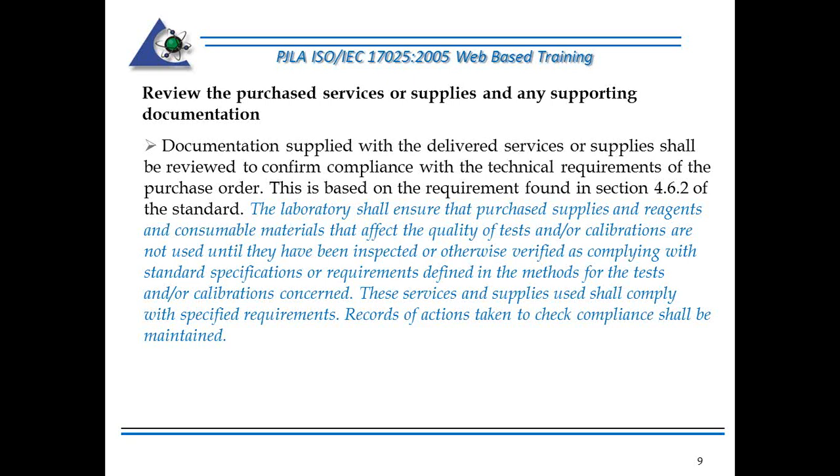So today we're going to be zeroing in on the fact that calibration certificates issued to your laboratories have to be evaluated as part of the 4.6.2 requirement. The way that you evaluate them is by knowledge of the 5.10 section of the standard, which defines what has to be included. 5.10.2 and 5.10.4 identify things that are unique to calibration certificates and have to be contained on them. 5.3 applies to test reports, but we're not talking about those today.